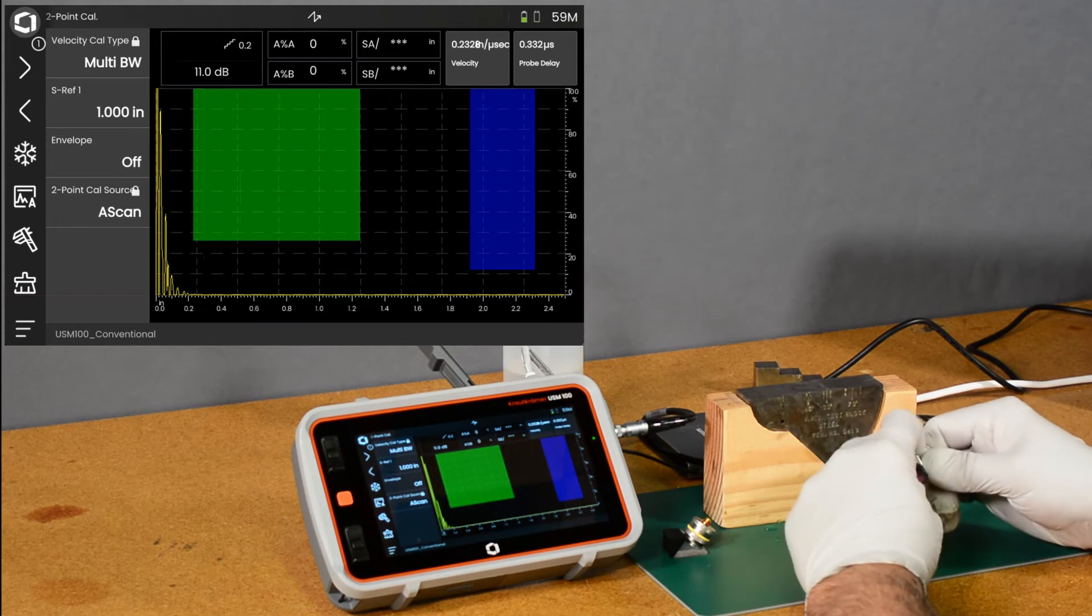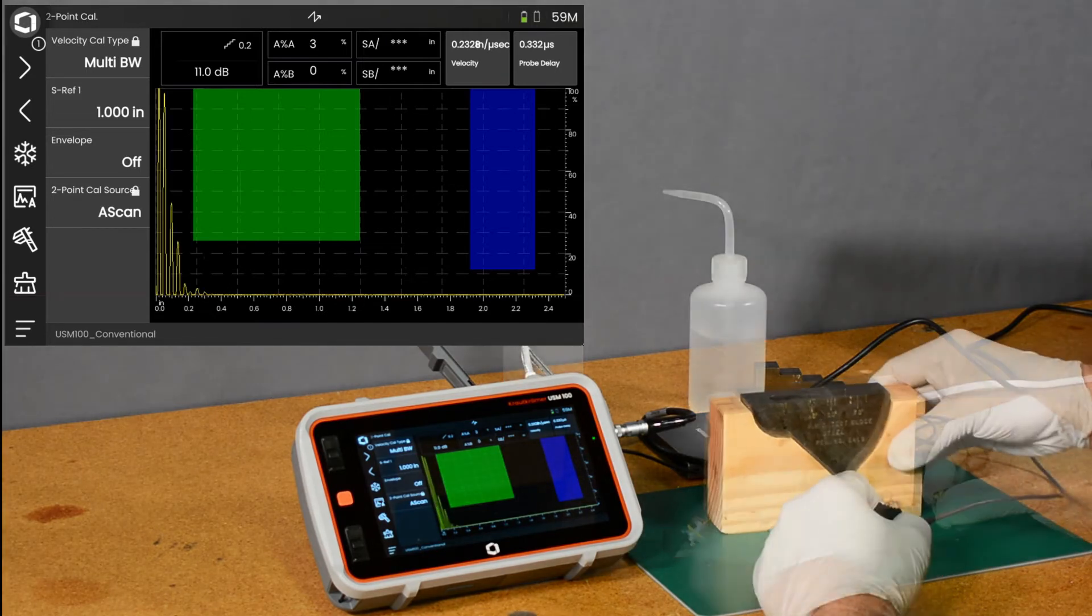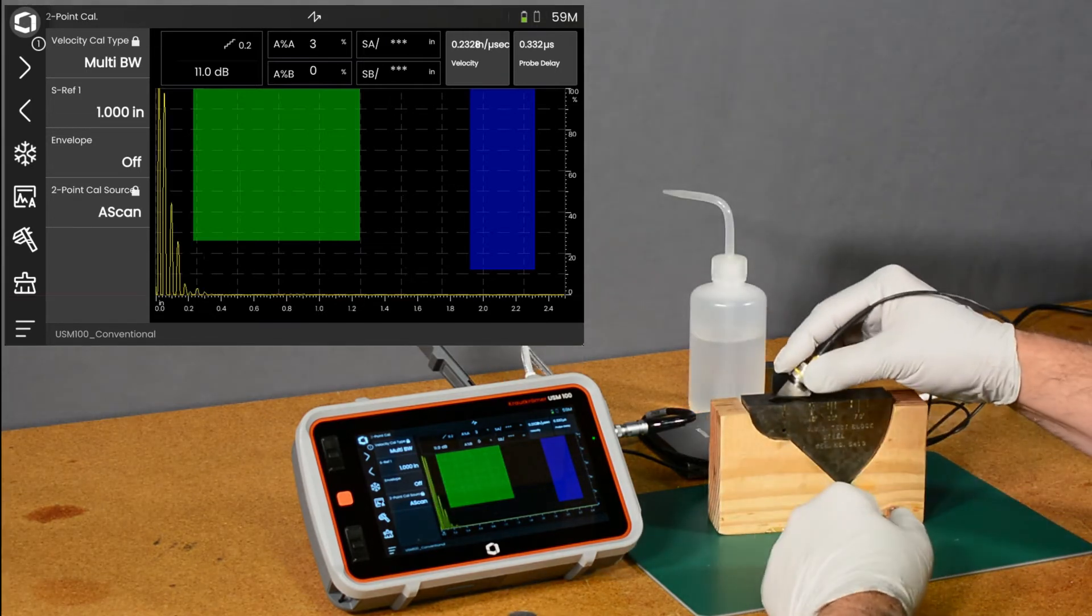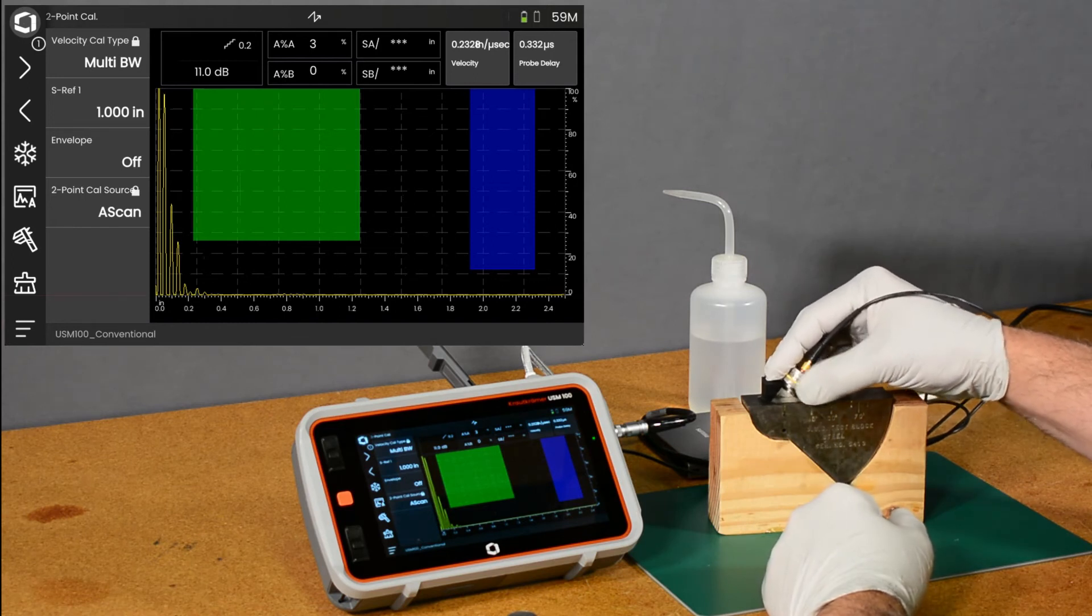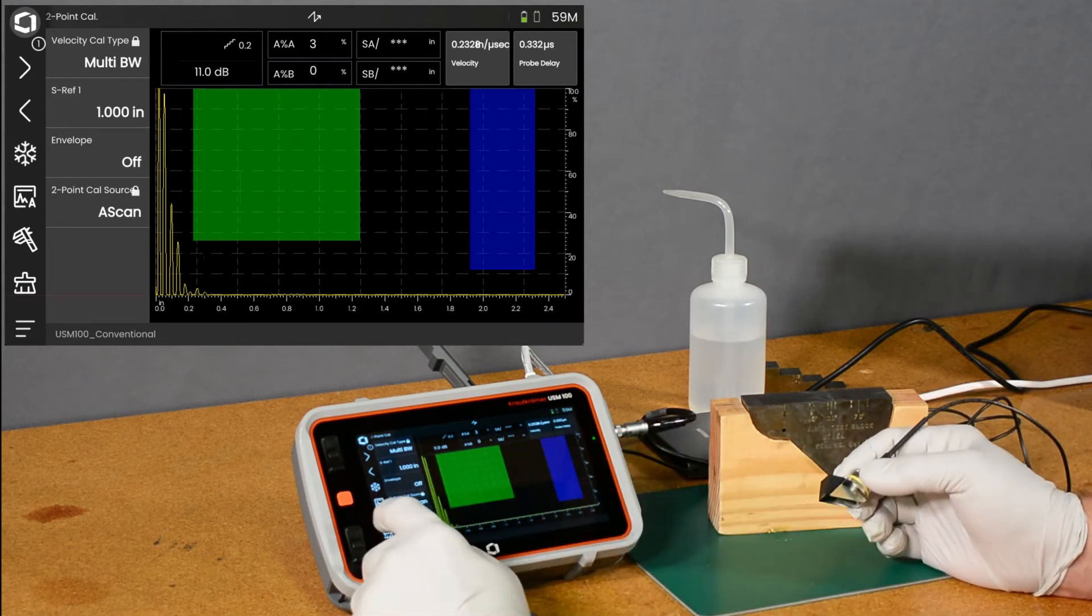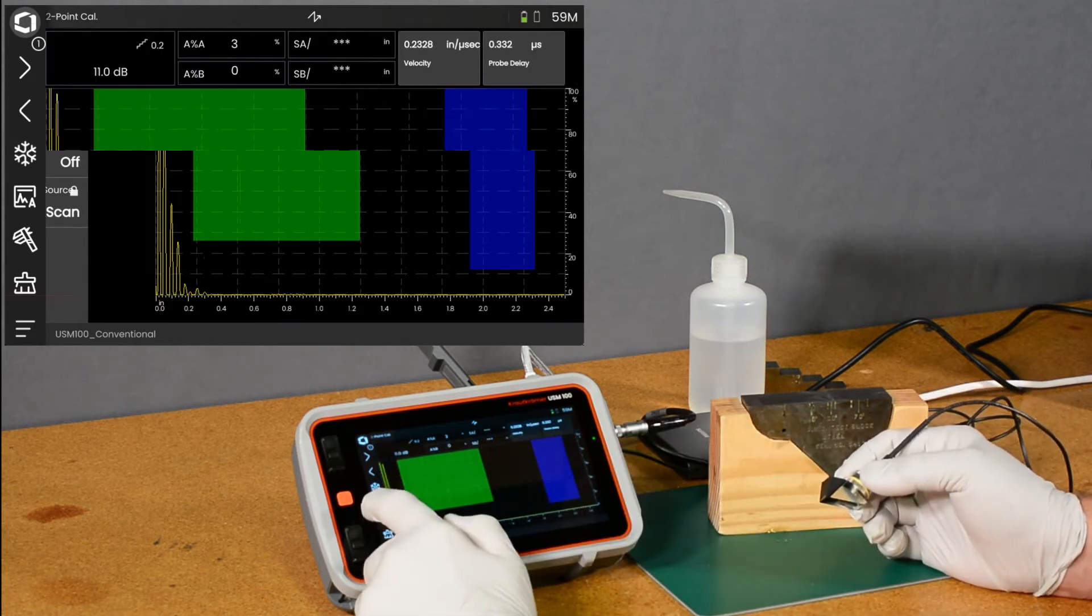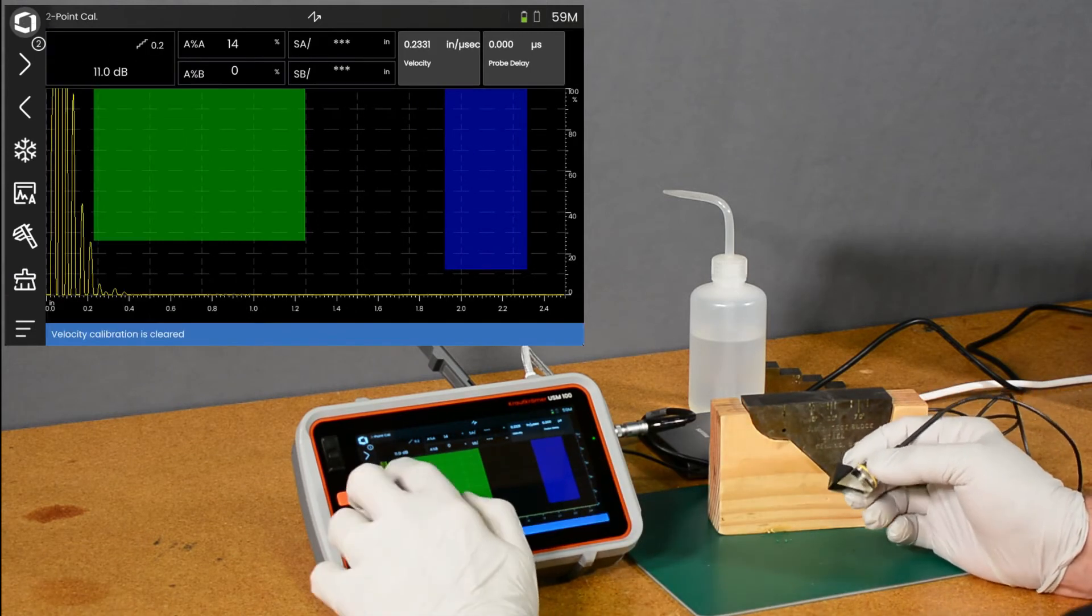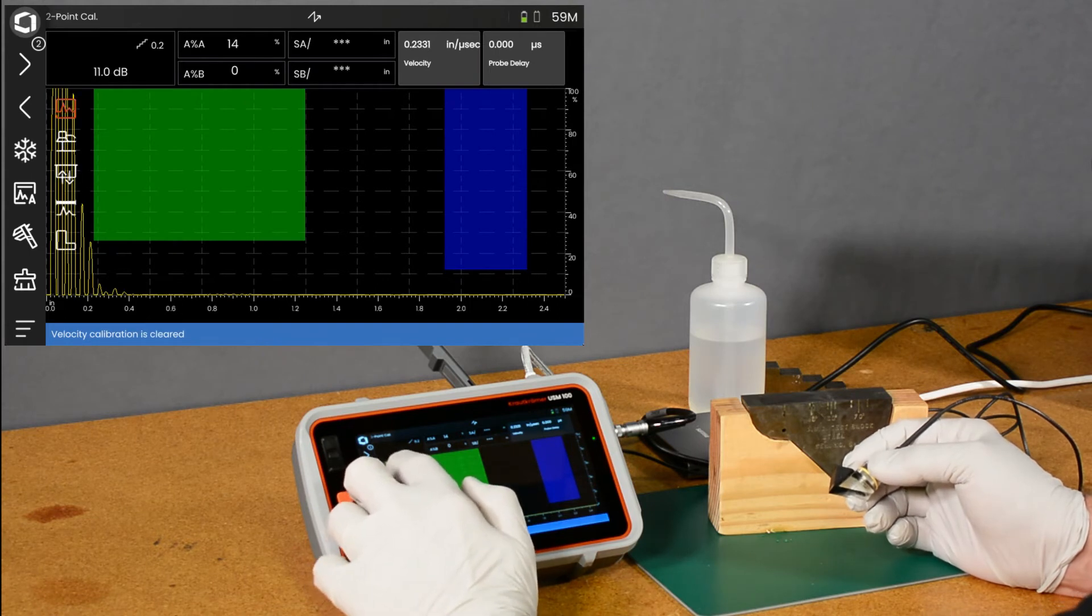So we'll change out our probe and set up. Now we're going to need to change a couple of things because this is, in fact, a two and a quarter megahertz probe.